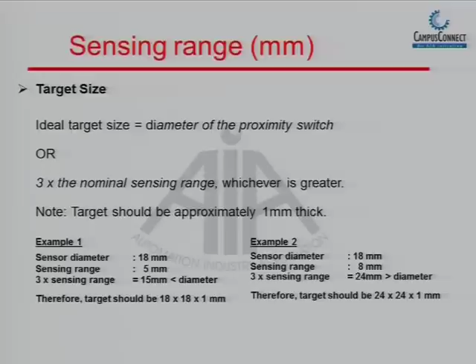That means that the oscillator will not be killed and we will not get an output. So, these are some of the calculations that we do. For example, if we are using an 18 mm diameter sensor and the sensing range of the sensor is 5 mm, we say 3 times the sensing range is equal to 15 mm. Since the diameter is greater, we go with the diameter. That means the target should be 18 by 18.